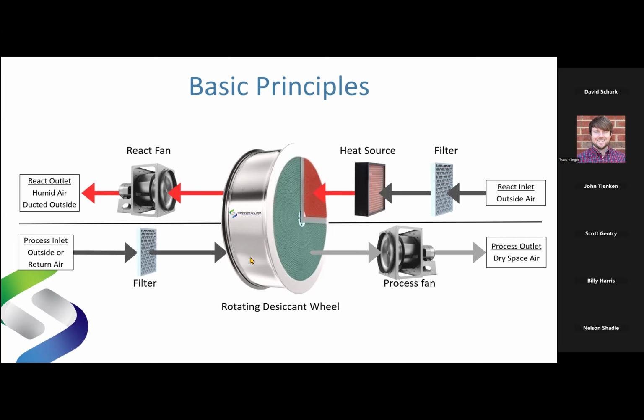We don't want any cross-contamination. I have in the center of a wheel a substrate material with flutes in it. Our substrate material is fiberglass. This wheel is about 12 inches thick. This wheel rotates at about 8 revolutions per hour, and this fiberglass substrate material is incredibly durable. If you go up and hit it with your fist, you are going to hurt your fist. You're not going to hurt the substrate material, nor will you dislodge any of the desiccant material that has been bonded to this fiberglass substrate material.